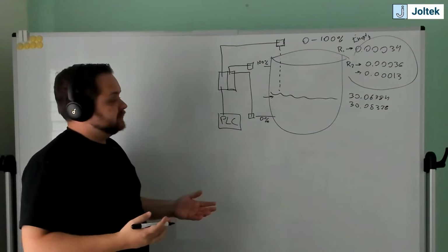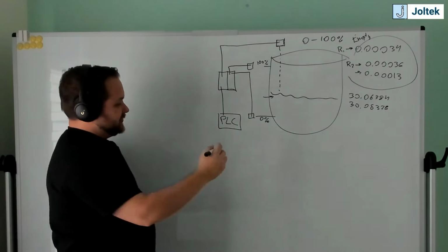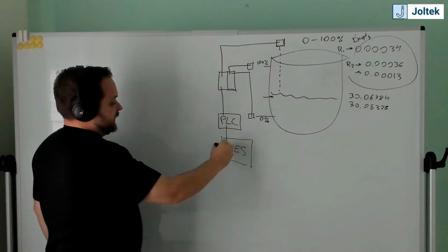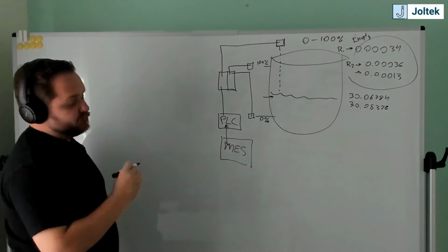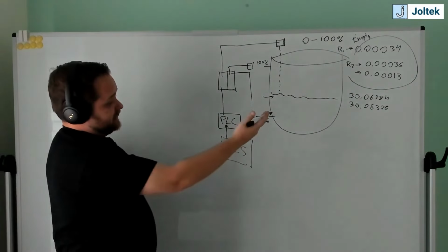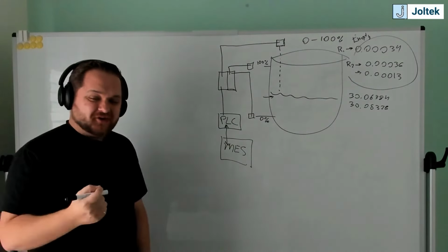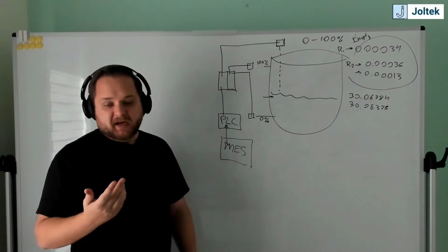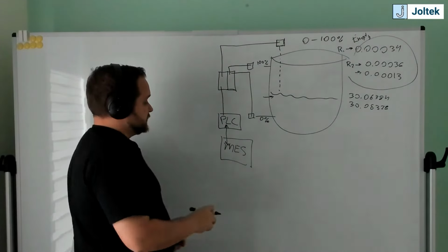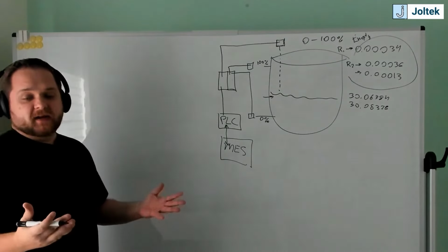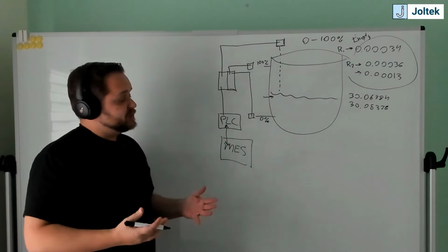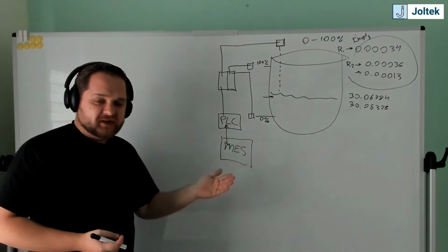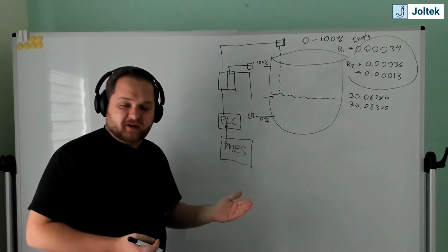So the first step is to understand that if you start sending that, imagine this is my MES, you're starting to send that as soon as it changes. And in this case, we define change as different signals. Then you're going to start stressing the system with packets at the millisecond or microsecond level. That would be even worse. Obviously here you have a switch. Why is that a problem? It is a problem, like I said, because you don't necessarily, number one, need that data, but you're also sending at a resolution that doesn't make sense, that simply creates traffic on your network.